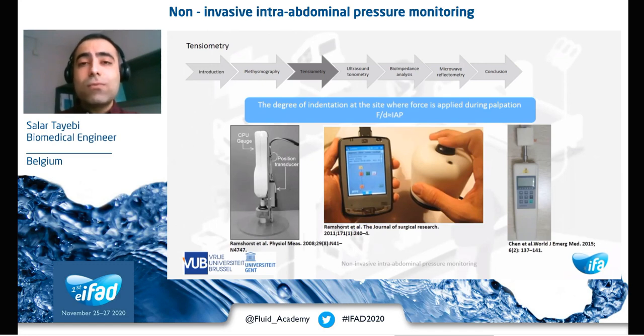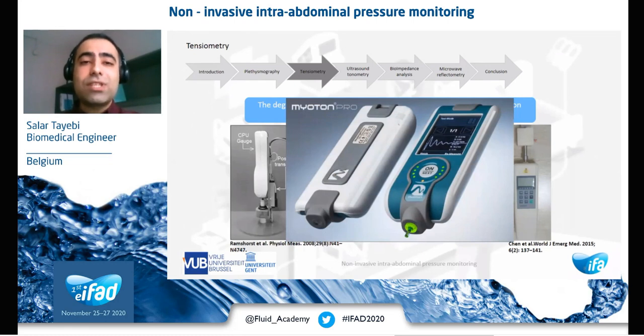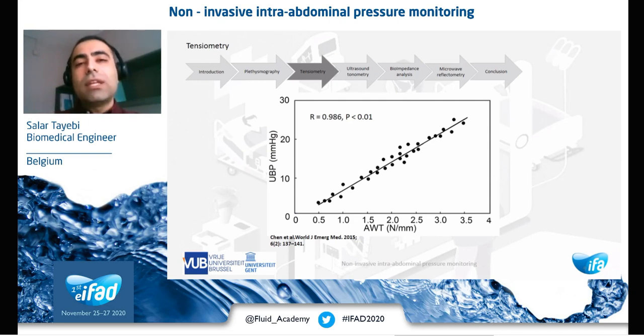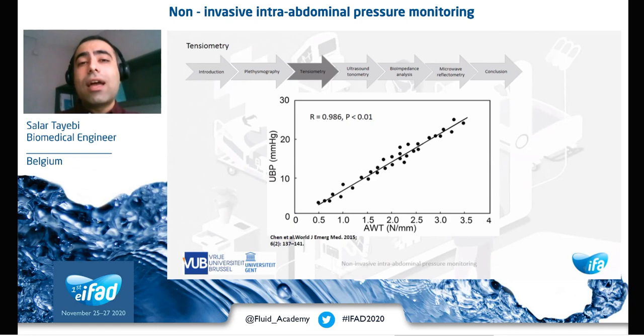Here you see different tensiometers used by different researchers. The main issue with this measurement technique was the lack of a standardized tensiometer, but this year a commercial tensiometer was introduced at Medica 2020 in Düsseldorf, capable of performing digital palpation at a standard rate. Here you see results from a study on 51 ICU patients investigating the correlation between abdominal pressure and abdominal wall tension. An almost linear correlation was found, with abdominal wall tension higher at larger abdominal pressure values.